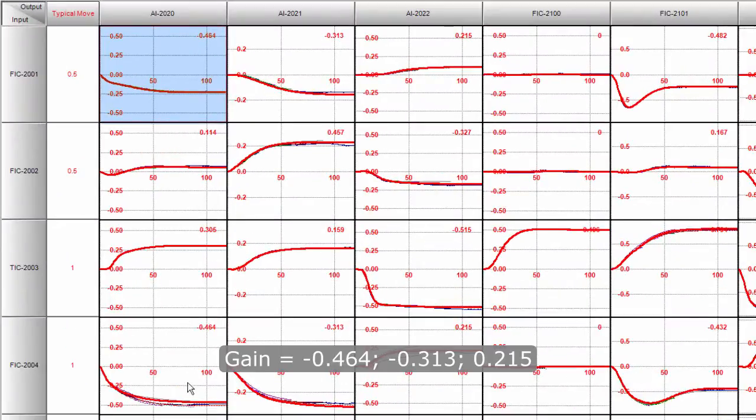Now we have the same gains for the top reflux and the mid reflux. That means the controller is not trying to move the top reflux more than the mid reflux and try to control those three CVs independently. They will be moving those two MVs together.